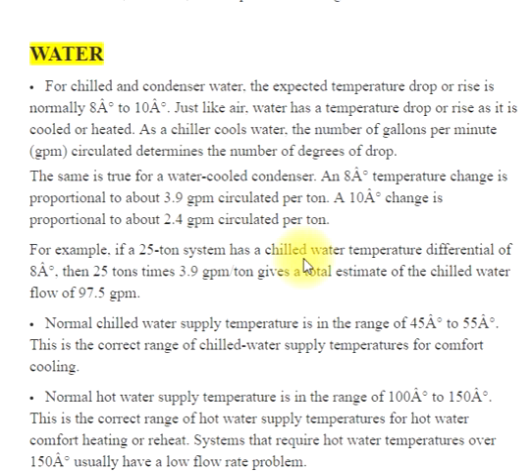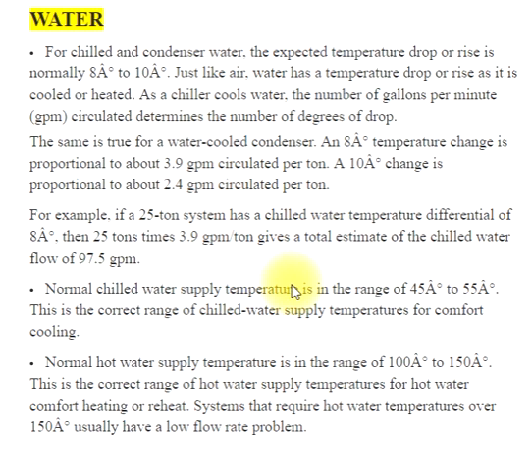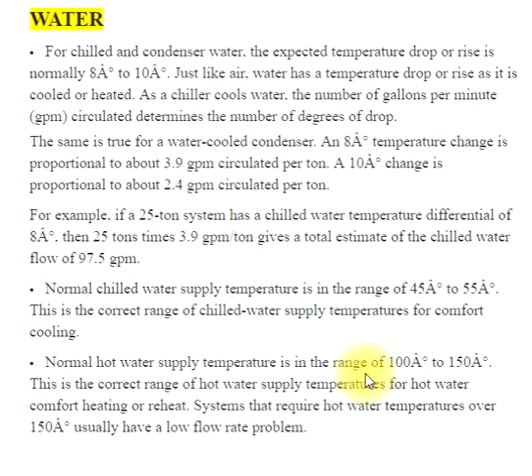For example, if a 25-ton system has a chilled water temperature differential of 8°, then 25 tons times 3.9 GPM per ton gives a total estimated chilled water flow of 97.5 GPM. Normal chilled water supply temperature is in the range of 45° to 55°F for comfort cooling. Normal hot water supply temperature is in the range of 100° to 150°F for hot water comfort heating or reheat. Systems that require hot water temperatures over 150° usually have a low flow rate problem.